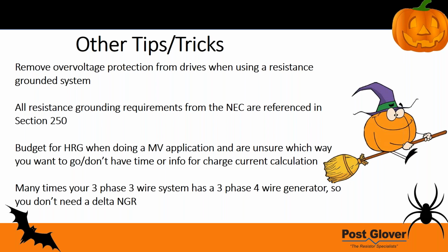A lot of times when these are in FEED, you're not going to have all the information you need. Another question I get all the time, or really it's a request: I get requests all the time for a Delta HRG system or Delta LRG system, either one. And it's for a 3-phase 3-wire system. So the one line says 3-phase 3-wire. Everywhere is 3-phase 3-wire. But it turns out that the generator is actually 3-phase 4-wire. Now you may not just know that from the one line, but the point is to check to make sure. You don't want to buy a Delta NGR, especially if it's high voltage, for an extra $10,000 to $20,000, then find out, oh whoops, we didn't need it. So that's what comes up all the time.